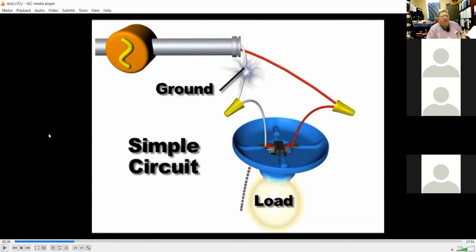Now, let me clarify something right here. The white wire there is a neutral wire, and the destination of it ends up at ground when it goes back to the breaker panel. But it's considered to be neutral, and whatever amount of current goes through the hot wire out to the light bulb, if it's a 60-watt bulb, it'll draw about a half an amp, as you'll find out when we get to Ohm's law. If you have a half an amp going through the hot wire to the bulb, it goes through the filament, lights the filament, and that same half an amp goes back on that neutral wire. So if you check the amps in each of the wires individually, the neutral wire also has a half an amp flowing on it. So it's called a neutral wire. It carries the same current as the hot wire does. It carries it back to the breaker panel.